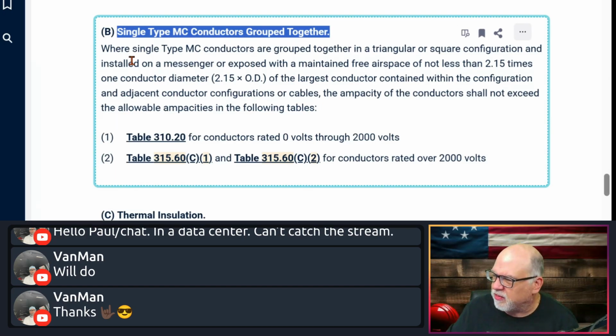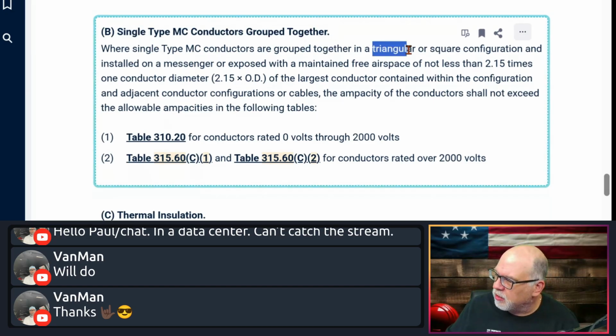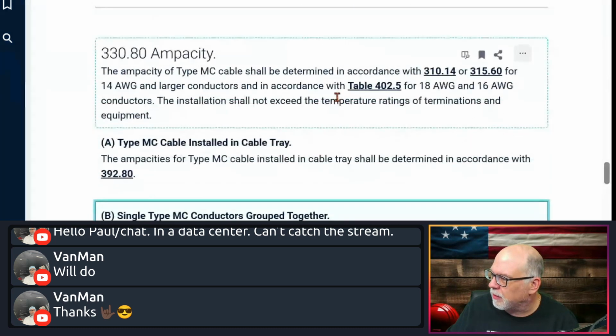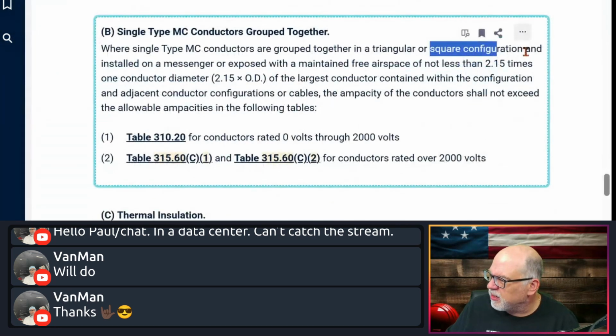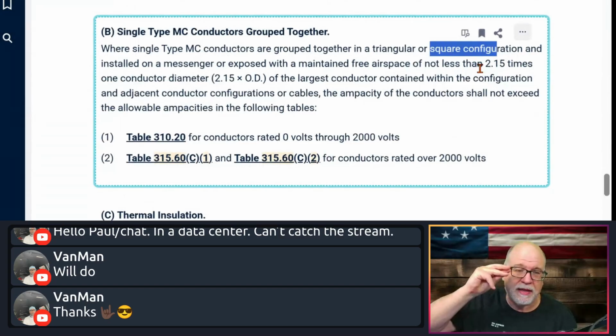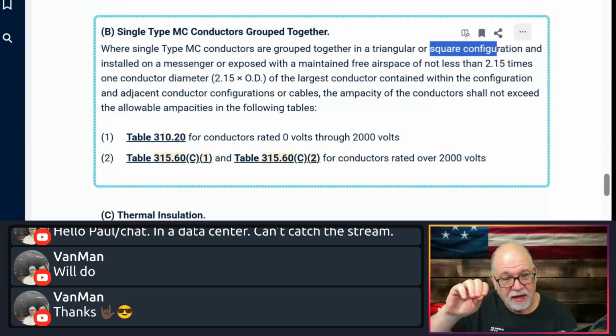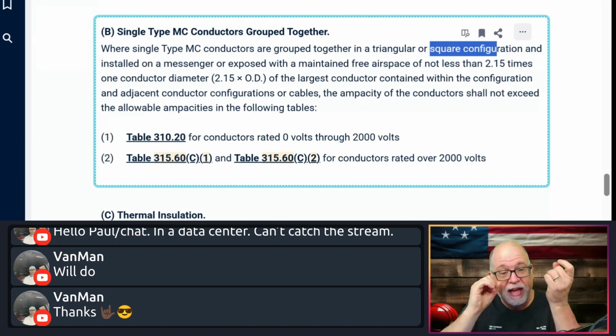That type of thing. So it says where single type MC conductors are grouped together in a triangular or a square configuration. Make sure where I'm at. I'm still in 330. Typically you're going to strap them together in a triad or a quad type of design in the tray or in installation in general, not just in a tray. You're kind of tying them together.